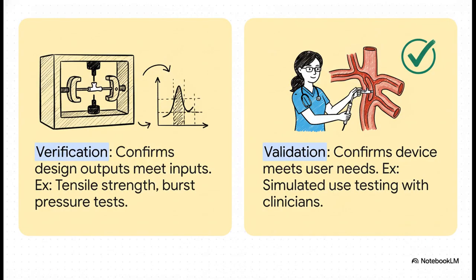Verification. That's all the testing you do in the lab. We're going to run a tensile strength test to see if the catheter breaks. We're going to do a burst pressure test on the balloon. It's black and white. It either passes or it fails. These tests directly answer those risks we identified earlier.